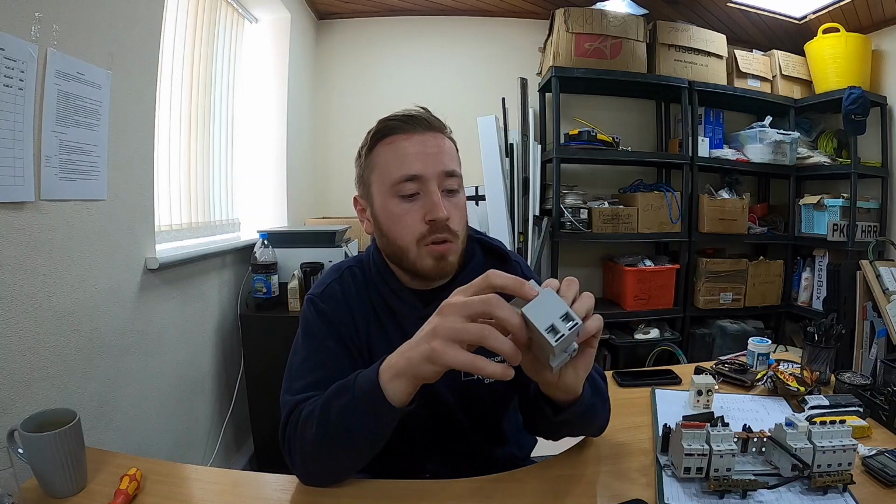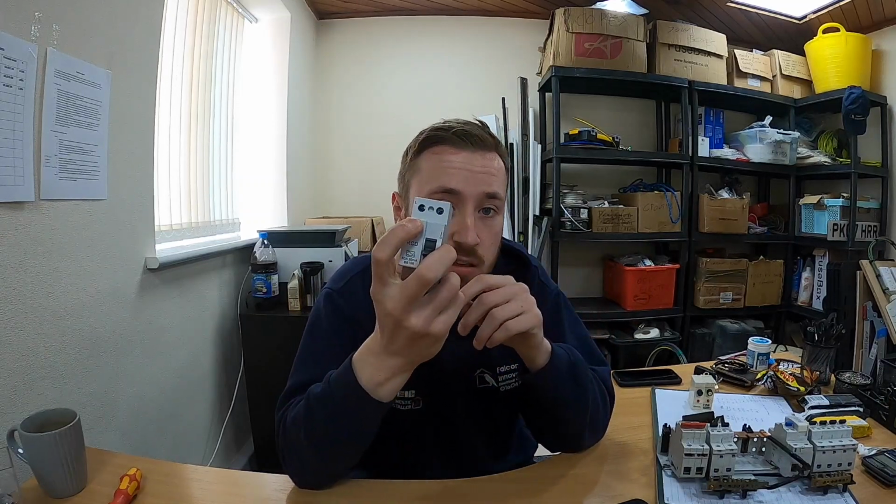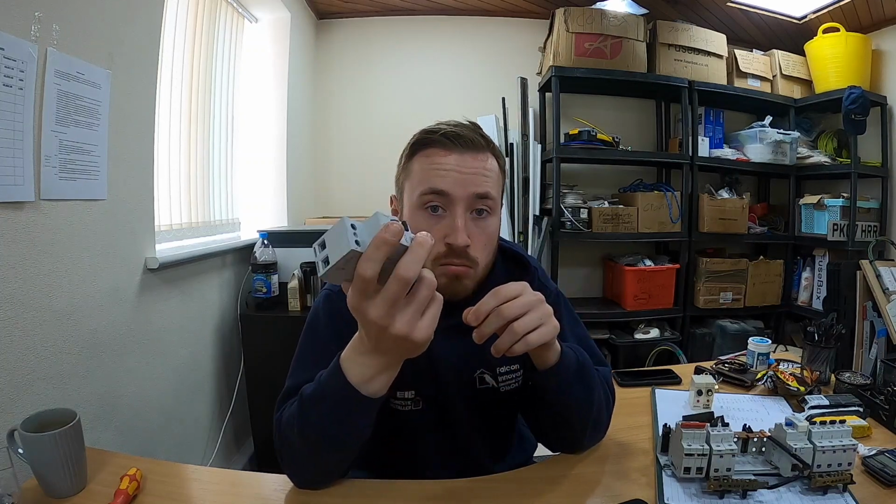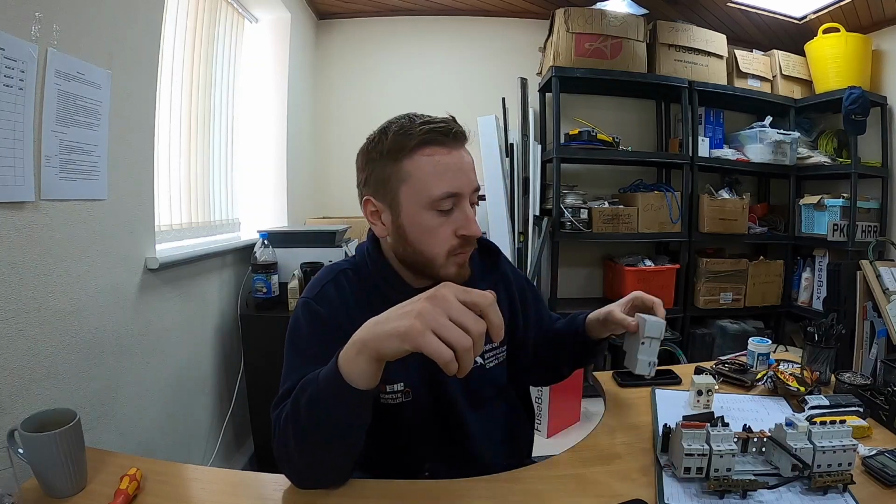This is known as an EICR, but what it basically tests against is the integrity of your property in modern conditions. So not when it was first installed, but if it actually meets regulations now. For example, you could have an RCD module in, could be completely fine, but if you haven't been testing the button regularly as the property owner, then this module might not actually trip out as required, which means it's going to fail. It's pointless having an RCD if it's not going to operate as needed to stop a problem.